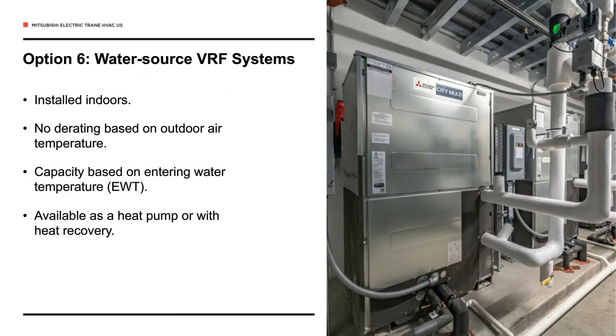Lastly, option 6 would be using a water source VRF system. Nice thing about water source VRF systems, similar to what I just showed you with placing the air-cooled units inside the building, the water source VRF system, everything is inside the building, at least everything from the VRF system standpoint. You're still going to have some sort of heat rejection device like a cooling tower or a fluid cooler. But the VRF equipment is installed indoors, so it's not getting rained on and hailed on and animal infestations into the equipment, things building nests, things like that. So equipment generally will last at least 5 years longer.